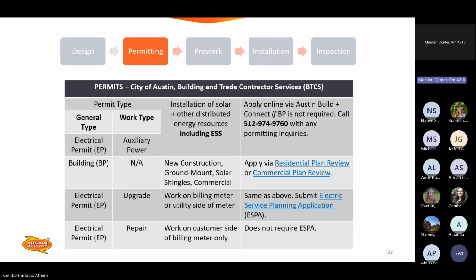So permits, you've got to have a permit. There are different types of permit. Auxiliary power is the type of permit we use for all PV system installations, so you will definitely need at least one auxiliary power permit for your system. That's as easy as it gets. If you've got work to do on the service, then you might need other electrical permits, service or upgrade permits. You'll need a building permit if it's new construction, a ground mount, or solar shingles, or if it's a commercial project. All commercial projects will need a building permit.